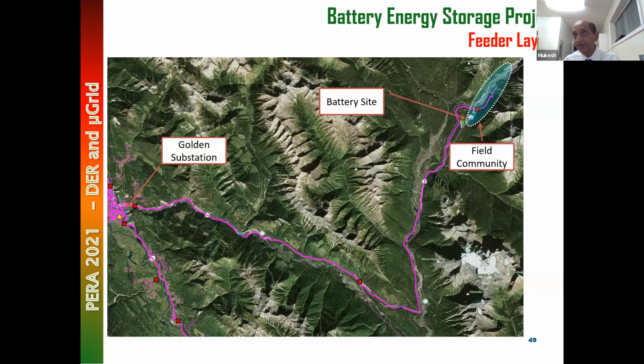So the community suffered many outages for many years. For many years, they lived with it. That's the best we could do. It was very expensive to put another alternative supply through a different path. Because of the terrain, it was not economically possible to serve this community, which has only a 1 megawatt load. For a 1 megawatt load, it was not practical to put in a second supply. Although all loads are important, you've got to draw some economic consideration. So we did really nothing. We had to live with it.